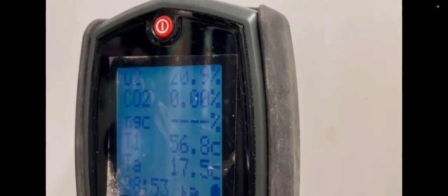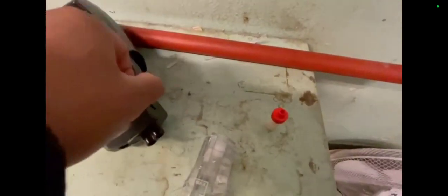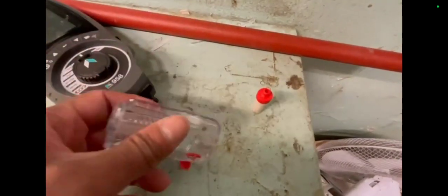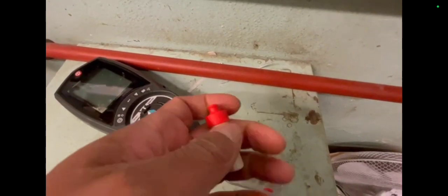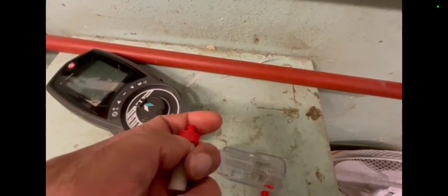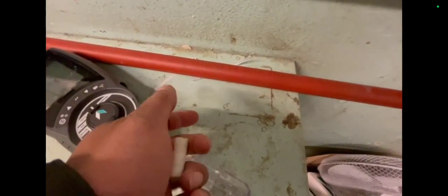Let's see if it's picking up any CO2 — it's not picking up any CO2. Still no readings from the analyzer. I took it apart and had a look at the filter and got the water out. I do need some new filters — this one is falling apart. I think my analyzer is due for calibration within a couple of weeks.